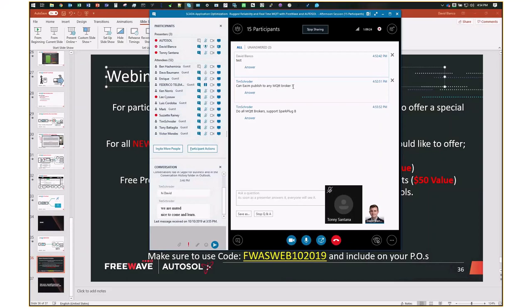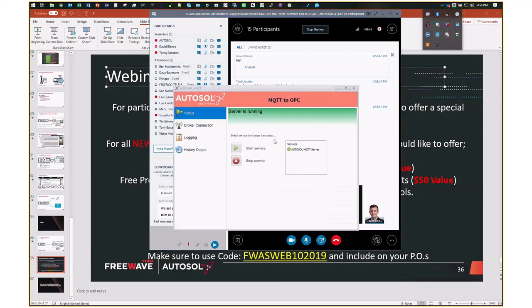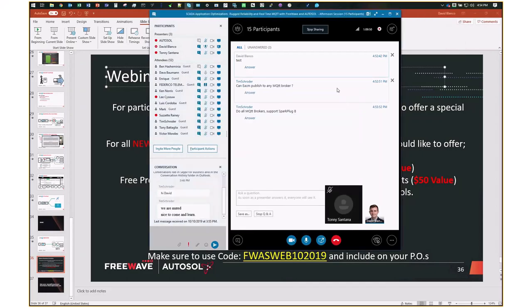Tim asks: Do all MQTT brokers support SparkPlug B? I can't be absolutely certain, but all the ones I've seen at client sites do. I've deployed Mosquitto, and on the system where we installed the ZumIQ behind MDS radios, we put Mosquitto on the network — it feeds data into that client's ClearSCADA system. HiveMQ is another that is MQTT SparkPlug B compatible. I think all the brokers that matter do work with SparkPlug B.